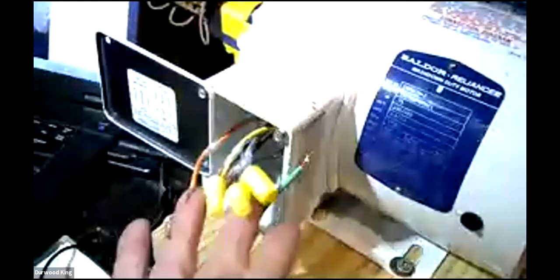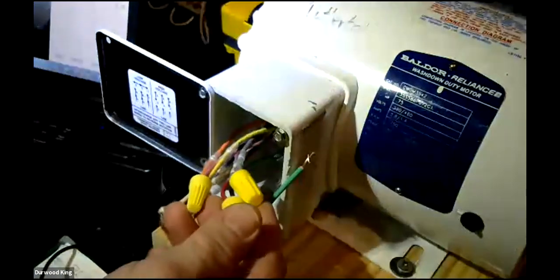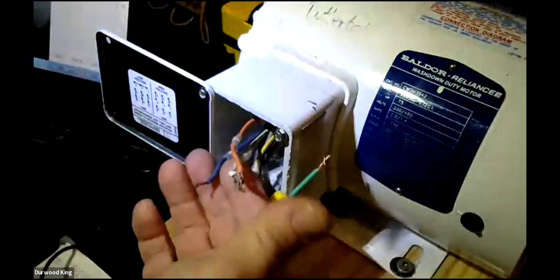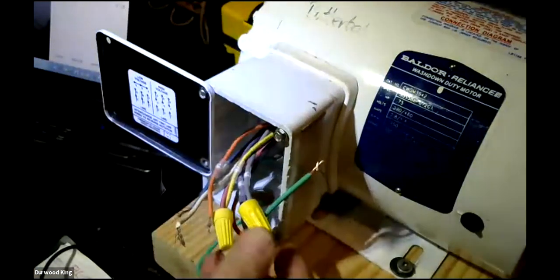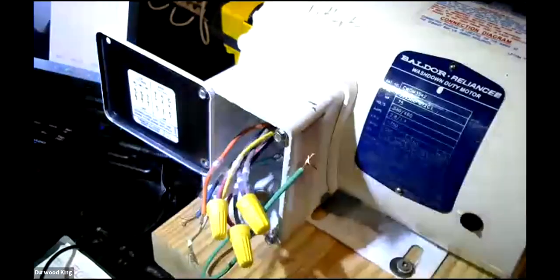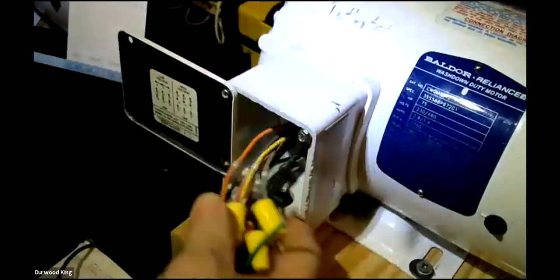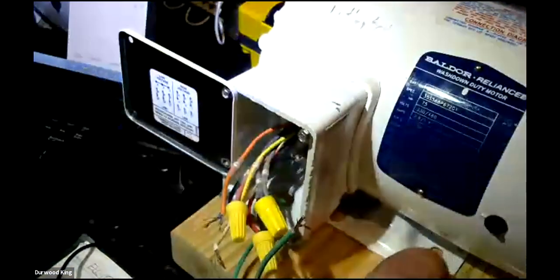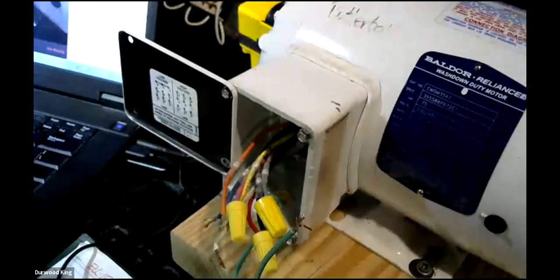Okay, now, so let's focus here now on the motor. I've got that motor. It's a 9-wire motor. I've got it wired high voltage, and I've got the 3 leads right here out here to where they can be tested. The motor's already been configured for high voltage again. That we did that earlier. And I have a ground wire here. Now let's take a look at the construction. There's 2 ways a motor could be wired, and let's take a look at them.